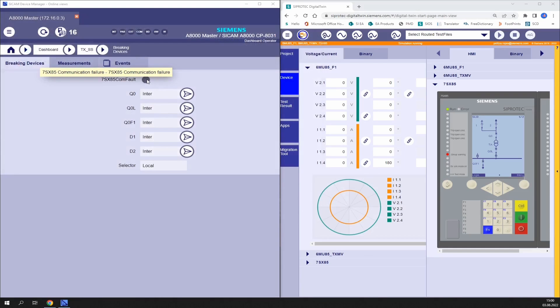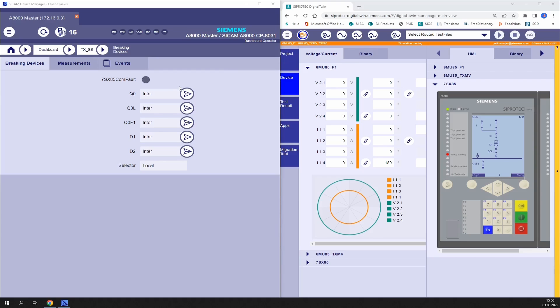Back to the SICAM A8000 user interface, we can see that the red LED has disappeared, meaning that the communication is up and the SICAM A8000 is receiving information from the simulated device in digital twin.